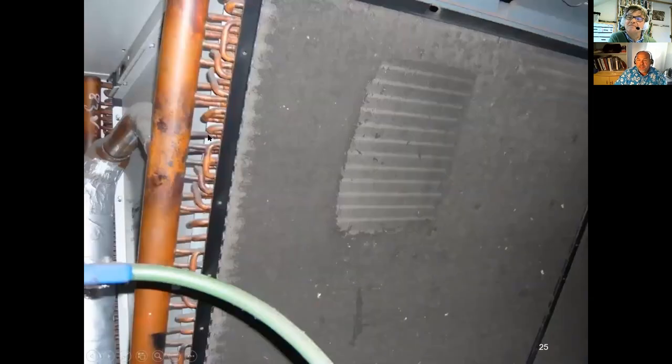When doing a survey, always look underneath the chiller. These York chillers are very good — they have a W or M configuration coil, and fifty percent of the heat transfer is underneath. I looked under the coils in London and basically scraped dirt off with a clipboard. Dirty coils will dramatically affect the efficiency of your chiller.